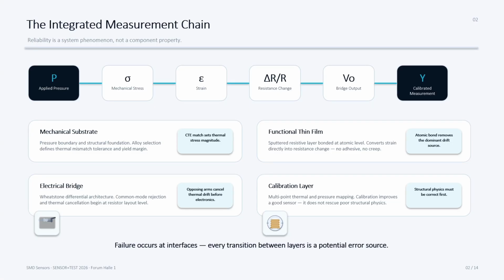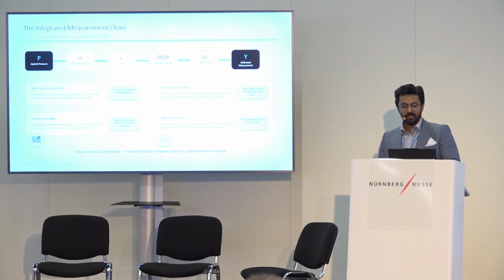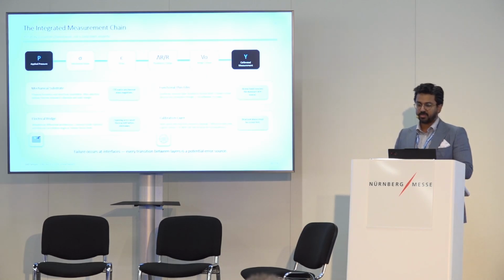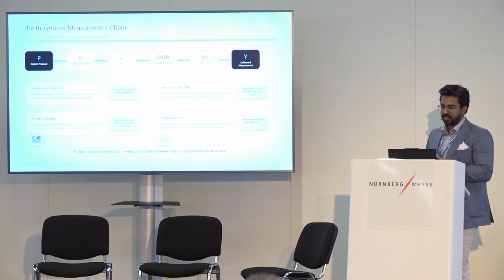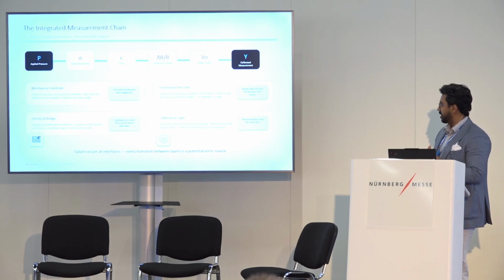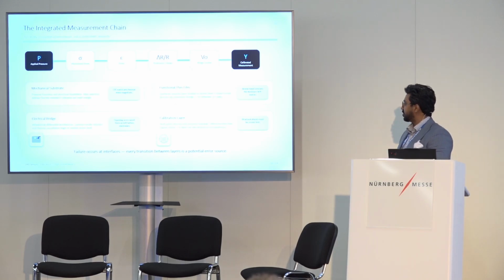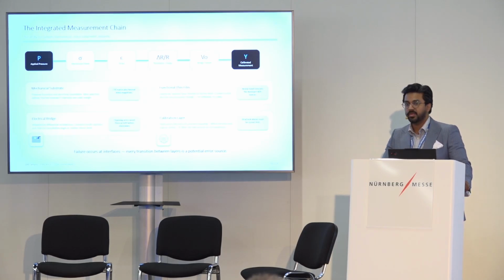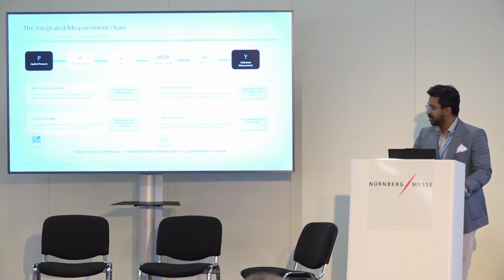So this is the heart of the talk in one picture. Pressure measurement is a relay race with six handoffs. Ideally, theoretically, pressure pushes on the diaphragm, that pushes stress in the substrate, which causes a strain, which then observes the resistive changes around it, creating a certain bridge output that could be verified with the electronics. A lot of calibrations are involved in all these processes.